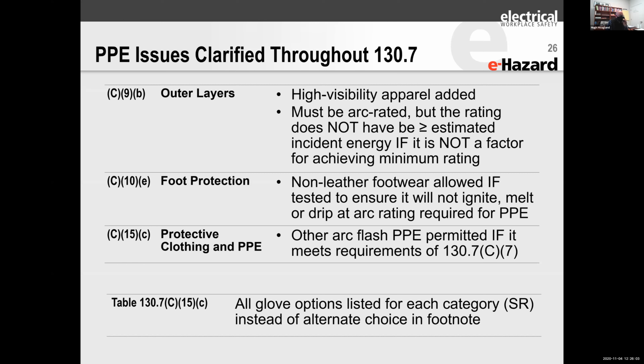You don't want to use these tennis shoe type safety shoes that are EH rated. They will melt onto you, but some of the really thick nylon type ones, or some that are partially leather and partially not leather, have been tested now. So get with your manufacturer if you want to use those type shoes. All leather, you eliminate any concern, but if not, you can have some freedom there.